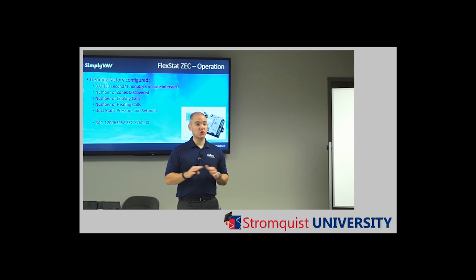The flex stat's no longer controlling room temperature, it's controlling DAT on the equipment. Okay. So if it sees that 9 zones need cooling and 7 zones need heating, we're going to default to majority wins, we're going to run our equipment in cooling mode, and we're going to control that equipment to maintain a 55-degree discharge of that equipment. So you still have the Simply VAV on the wall. Yep. And then you have one flex stat for every 16 zones. Yep. One flex stat for every piece of equipment, and it's looking at DAT versus onboard room temperature.